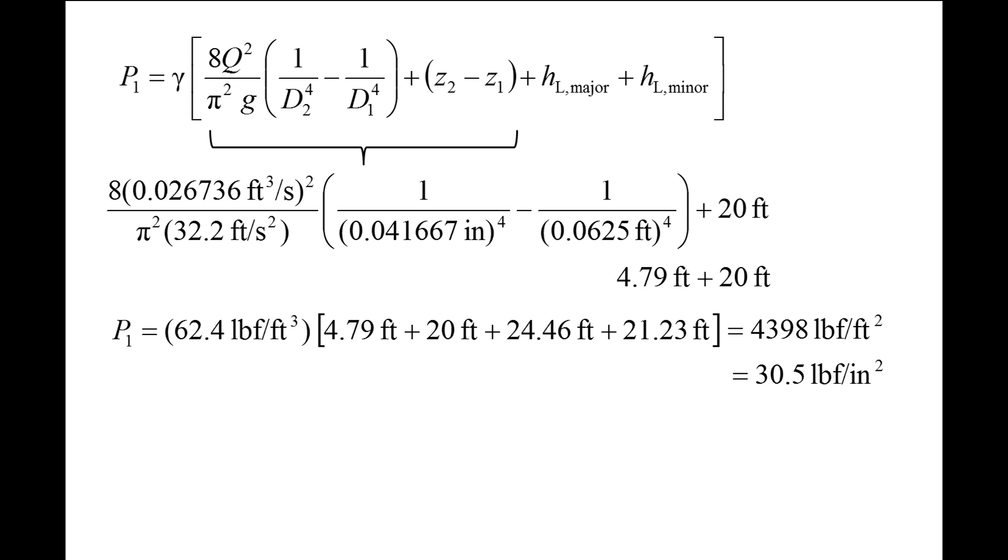We can obtain additional insight into this problem by examining the pressure associated with each term in the equation. If we multiply the major head loss, 24.46 feet, with the specific weight, we obtain 10.6 psi. This means 10.6 psi is required to overcome the frictional losses due to the straight pipes. If we multiply the minor head loss, 21.23 feet, with the specific weight, we obtain 9.2 psi. This means 9.2 psi is required to overcome the frictional losses due to the six components.